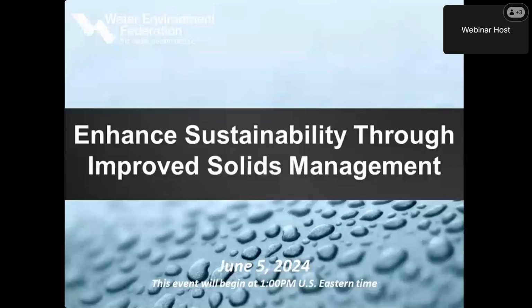Any concerns about Vivianite precipitates in digested sludge and iron precipitation on UV? As far as enhanced dewatering is concerned, the answer is no. As far as Vivianite, I've never personally experienced it. Iron precipitation on UV when you're dealing with enhanced dewatering, we obviously optimize the application to ensure that there is no free iron remaining. So the answer there is no.